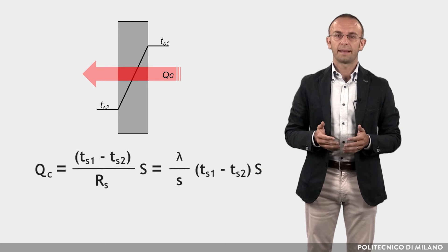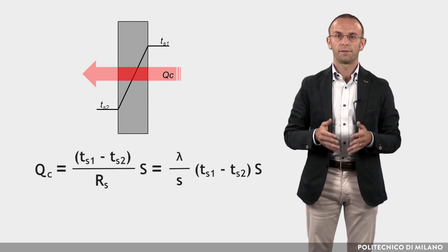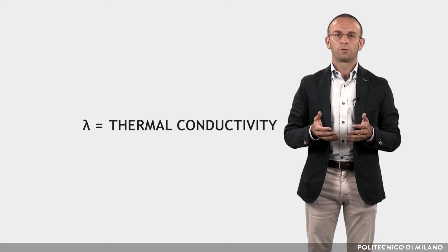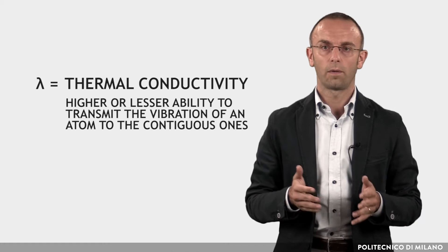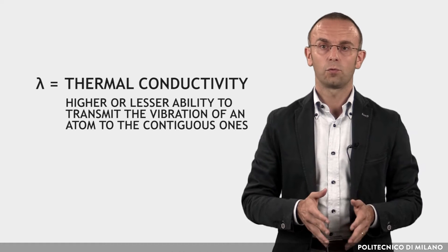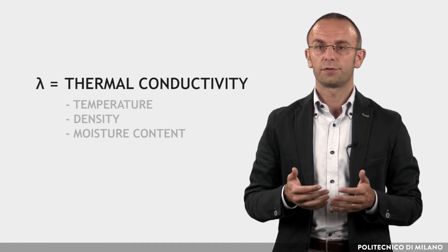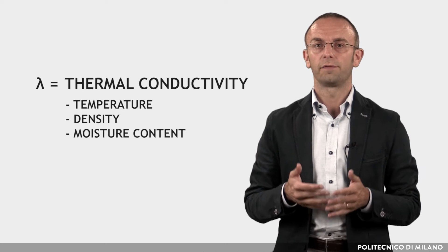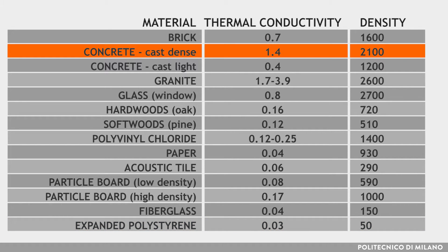The flux is directly dependent on the temperature difference and inversely dependent on the thermal resistance, and thus on the conductivity. The thermal conductivity is a specific property of each material and defines the higher or lesser ability to transmit the vibration of an atom to the contiguous ones, which means to conduct the heat from one point to the other. It is dependent on the temperature, the density, and the moisture content of the material. Typically, low density materials such as polystyrene have low thermal conductivity, while materials with high density such as concrete have elevated thermal conductivity.